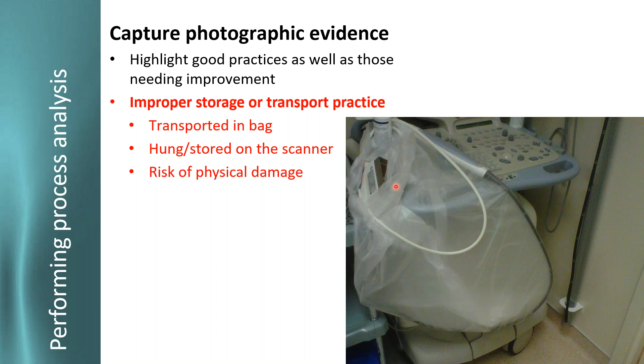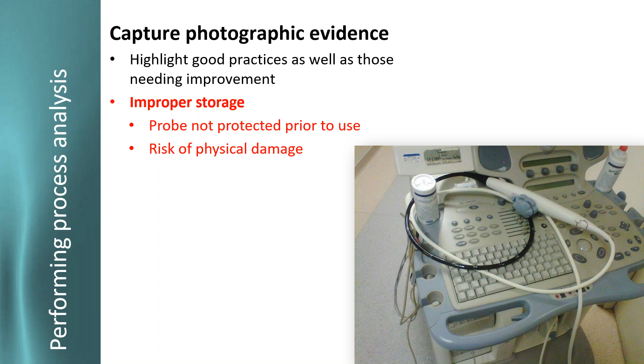The connector is kind of hung. There is a dramatic risk of physical damage doing this. Same with this. We have our tip very tightly coiled across the keyboard, and this could be damaging the keyboard. There are toggle switches. This particular system is a GE Vivid 7. As they move this probe around, you can actually damage the console of the machine as well. So we don't want to do that for a variety of reasons.